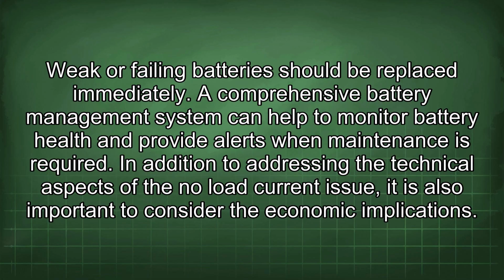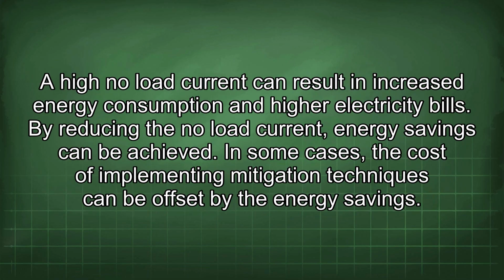In addition to addressing the technical aspects of the no-load current issue, it is also important to consider the economic implications. A high no-load current can result in increased energy consumption and higher electricity bills. By reducing the no-load current, energy savings can be achieved. In some cases, the cost of implementing mitigation techniques can be offset by the energy savings.